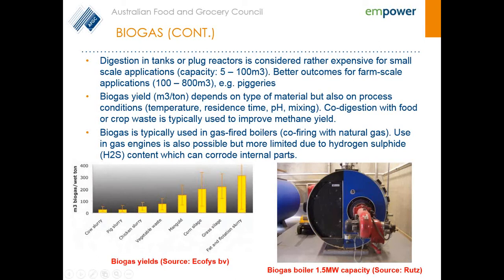As mentioned in the previous slide, digestion tanks or continuous stirred-tank reactors are considered expensive for small-scale applications — we're talking perhaps up to 150 cubic metres, though we've seen better outcomes in some farm applications between 100 and 150 cubic metres. The lagoons are much less costly but require a significant amount of space, and not all processing facilities can treat wastewater in an anaerobic lagoon. Those are the things that will have to be considered.